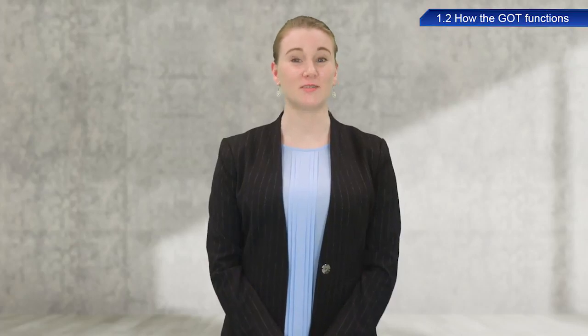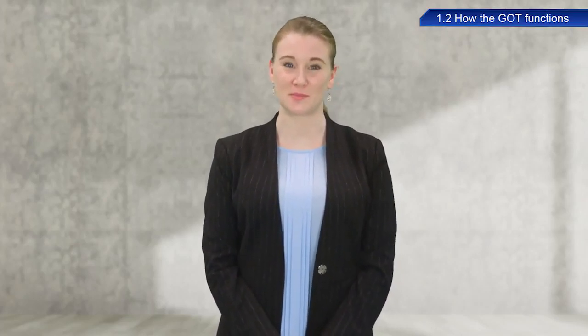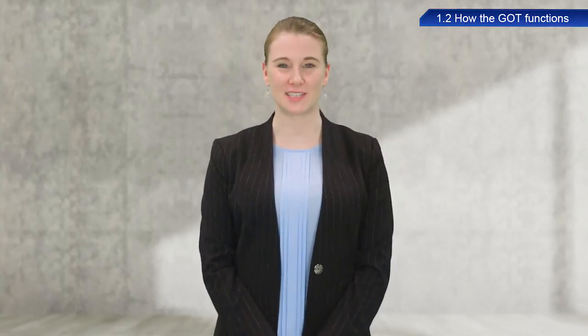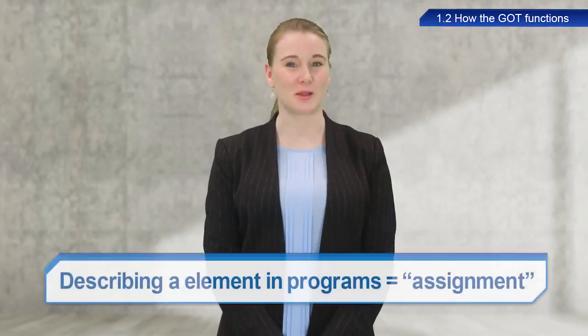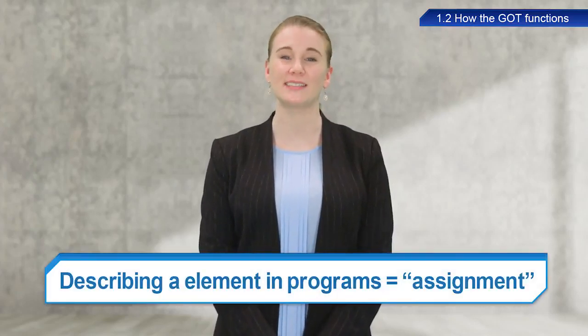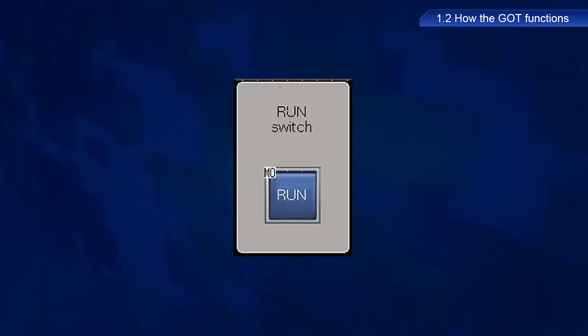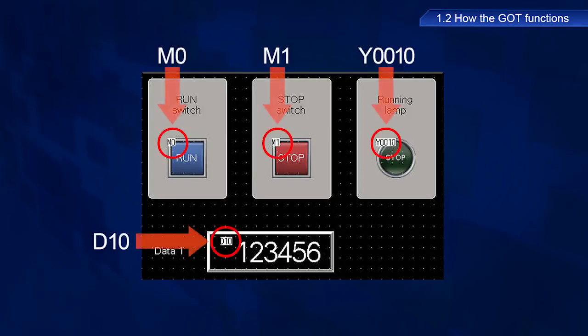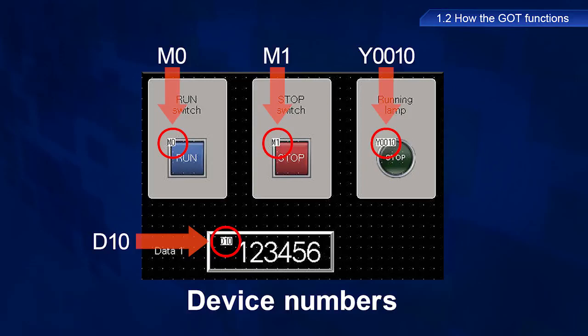Do you now have a better understanding of the relationship between GOTs and PLC programs? GOT switches and lamps must be described in PLC programs to have functionality. Describing these elements in programs is referred to as assignment. The text string M0 has been assigned to the GOT run switch. These assigned text strings, such as M0 and D10, are referred to as device numbers. Device numbers are assigned to other switches and lamps in the same way. Please remember these terms as they will continue to be used throughout this training.